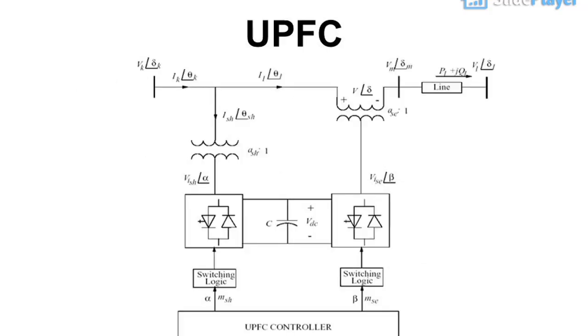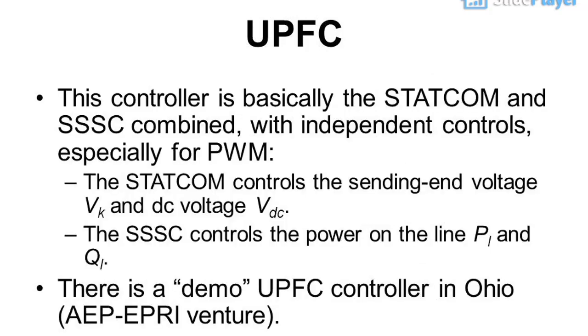UPFC: this controller is basically the STATCOM and SSSC combined, with independent controls, especially for PWM. The STATCOM controls the sending-end voltage V_K and DC voltage V_DC. The SSSC controls the power on the line P_L and Q_L. There is a demo UPFC controller in Ohio.